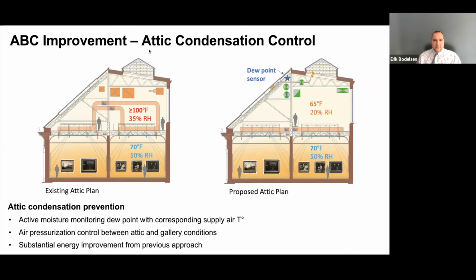The section on the right indicates the new design conditions. We were able to substantially reduce the heating requirements throughout the vast attic while still controlling condensation. This was achieved with, first and foremost, the improved skylight glazing and framing system Michael discussed, as well as active moisture monitoring of the dew point with corresponding variable supply air temperature and air pressurization control between the attic and the gallery conditions. Next slide, please.